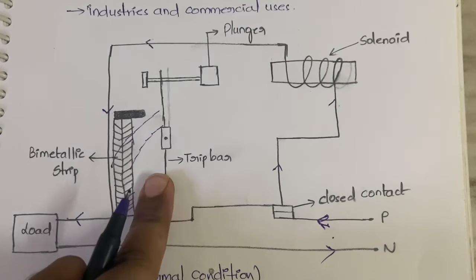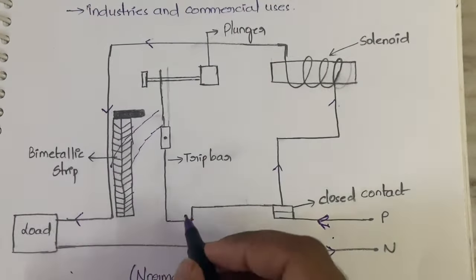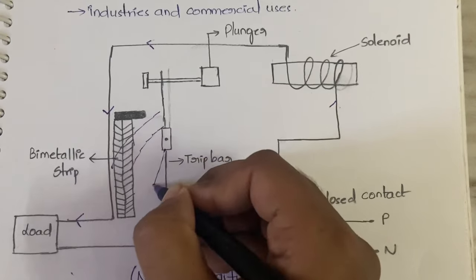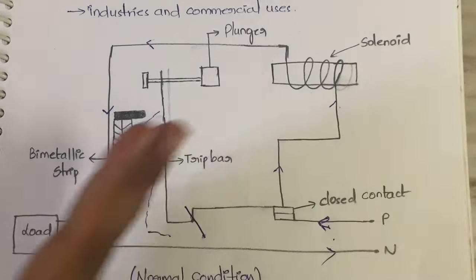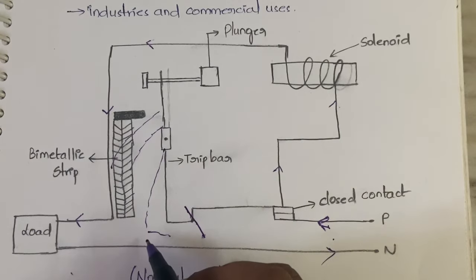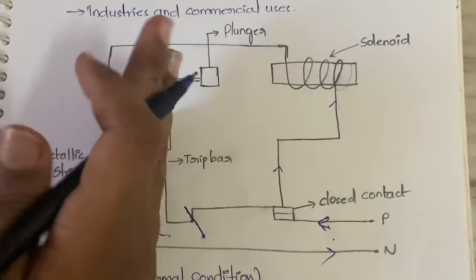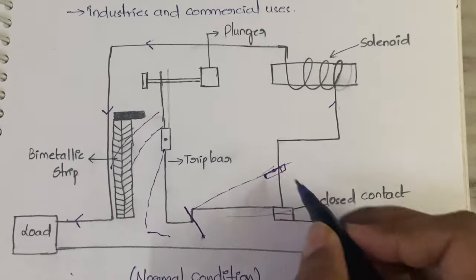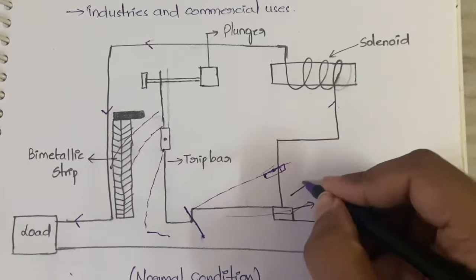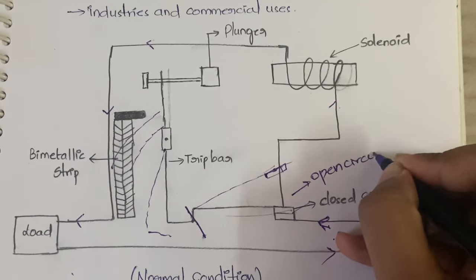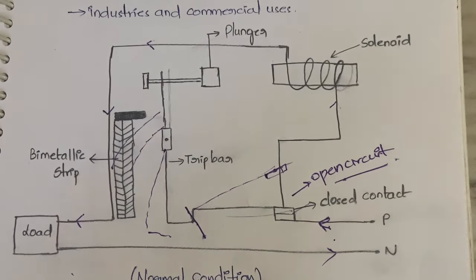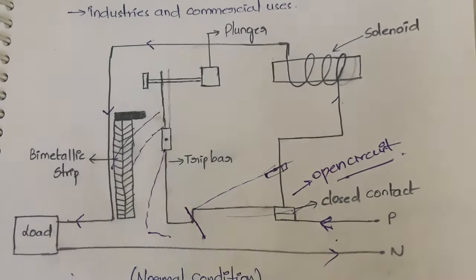When the bimetallic strip hits the trip bar, the trip bar will move from its position — it will displace. The contact that was closed will be broken. The trip bar displaces and this closed contact opens up, so it becomes an open circuit — no current will flow. As a result, the load is safe and no harm is done to it.